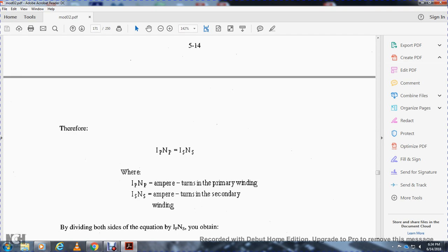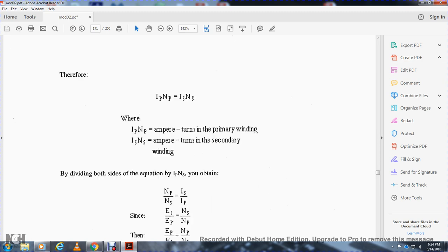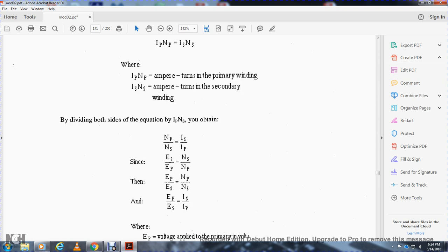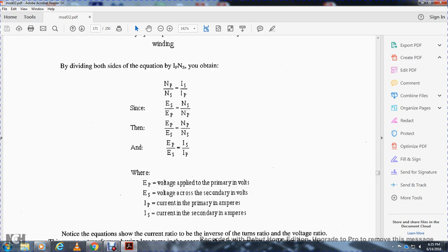Turns and current ratios: the number of flux lines developed is directly proportional to the magnetic force, measured in ampere-turns. The ampere-turns is amps times number of turns, measuring the magnetomotive force — defined as the force developed by one ampere of current flowing in a coil of one turn. Since the flux in the transformer core surrounds both the primary and secondary windings, the ampere-turns of the primary and secondary windings must be equal. Therefore: amperes × turns in primary winding equals amperes × turns in secondary winding.